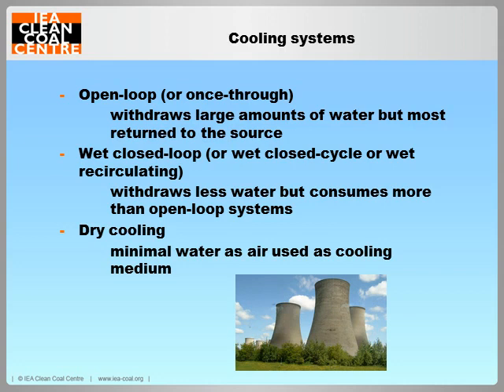Wet closed-loop systems, also called recirculating systems, withdraw less water than open-loop ones, as the heated water is cooled through a wet tower or pond and reused. Most of the withdrawn water is lost through evaporation, so water consumption is higher than in open-loop systems.